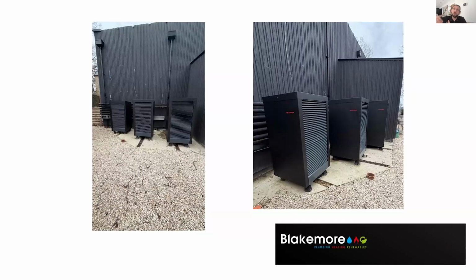This job was already ongoing, so they'd already had the underfloor done. Everything was 150 mil centres everywhere, no matter what floor finish, no matter what size room. It was not done great, so we've had to try and work backwards from that. On a project this size, that's been quite a challenge because it's already in the floor, concreted and screeded over.